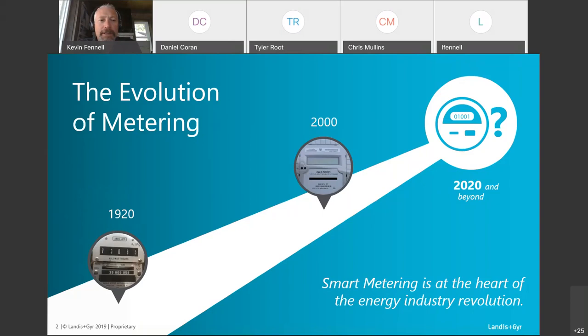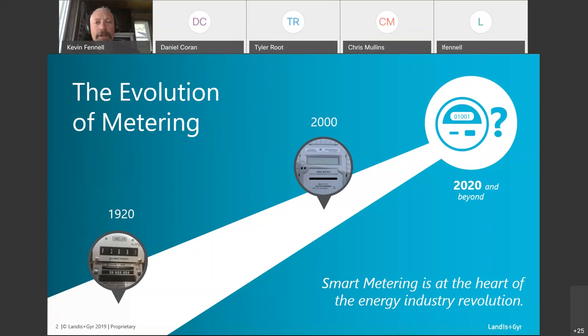I've given you a perspective here of 100 years of metering. The round meter that we have on our homes today in the US was actually envisioned between 1910 and 1920 by an ANSI committee. ANSI C12 came up with a specification for what we have used for 100 years as a round meter. We needed a standard so we could plug it into an S-based socket at any premise — for single-phase service it's a form 2S, apartment buildings get 12S, commercial gets 9S and 16S. It's a physical standard where safety is a must.